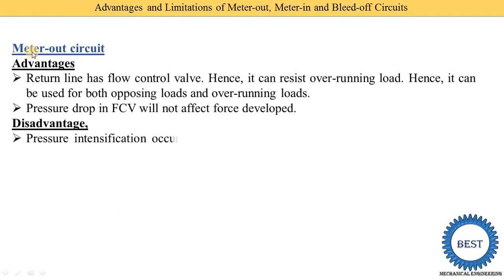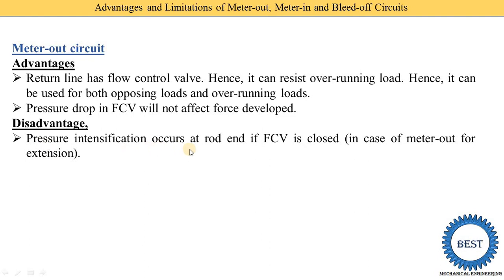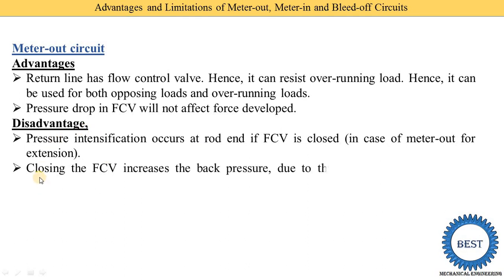Now, what are the disadvantages of the meter out circuit? Pressure intensification occurs at the rod end if the flow control valve is closed. During the extension stroke of the meter out circuit, if we close the flow control valve, pressure intensification occurs at the rod end. The second disadvantage: closing the flow control valve increases back pressure, and due to this, the net force developed will be reduced.